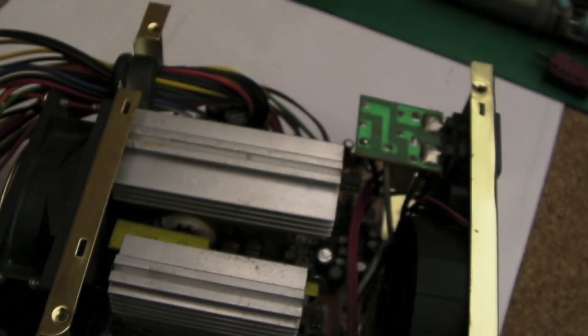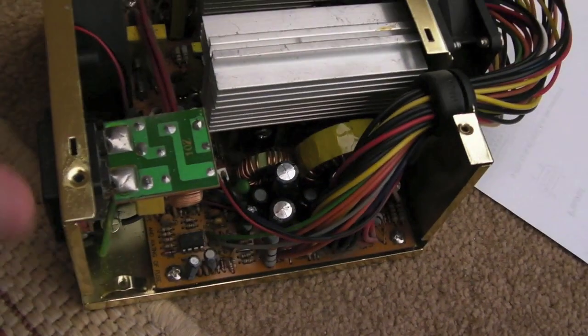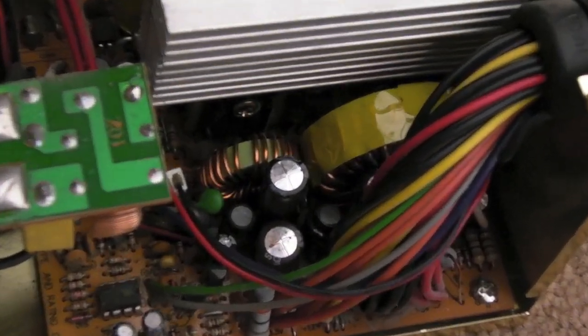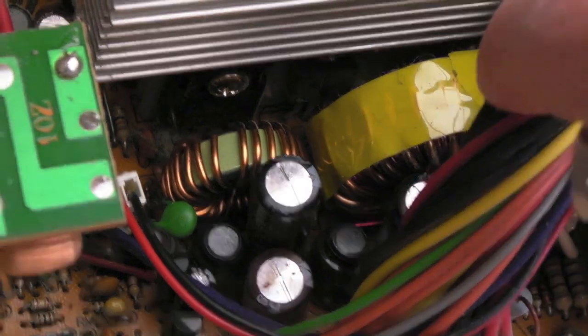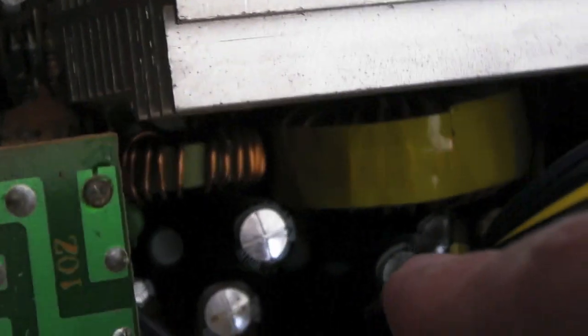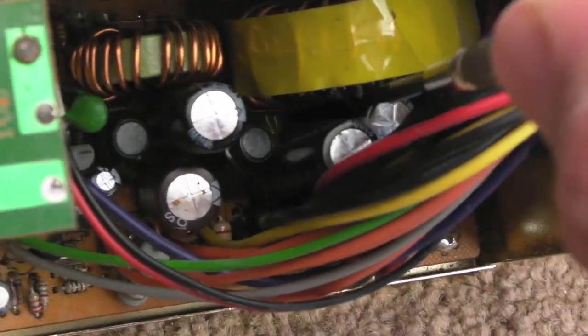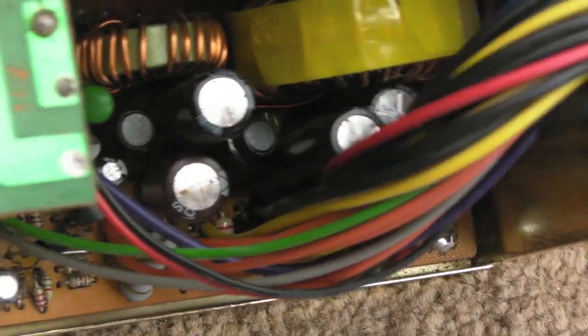I'll take the lid off and hopefully you can see if I just zoom in down here. See, swollen caps. So yeah, down there that one's - sorry, off camera a little bit - that one there bulging as well. So certainly these caps around here, certainly these four need swapping out. I'll check some of the others as well.